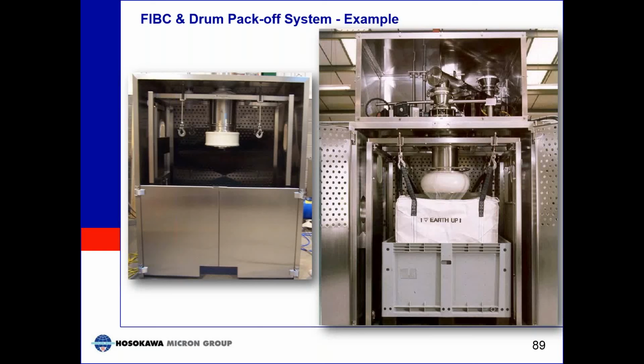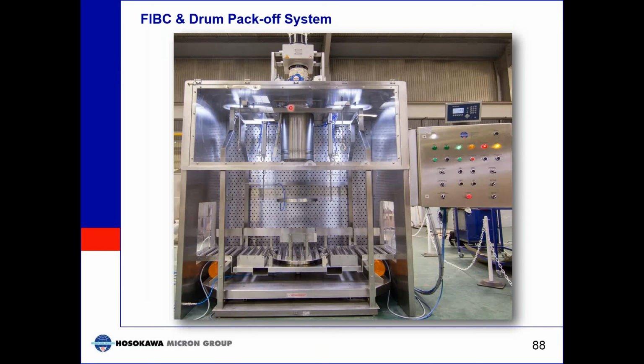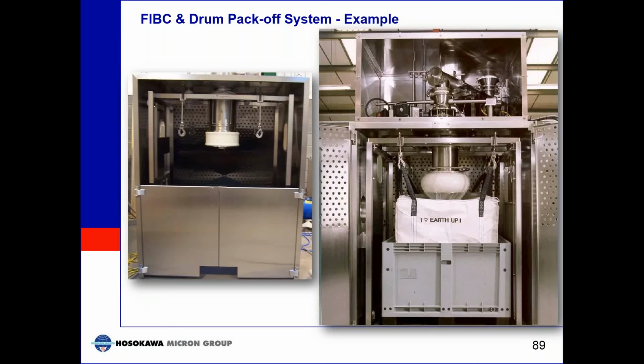In achieving that make-up air, there might be limitations on the HVAC, for instance, so that the room has only got a limited supply of make-up air. In those instances, the ½ meter a second airflow would only be on the aperture between the lower doors and the upper screen. So, as shown here, the gap between the two, where the operator can still have access to the liner and can still tie the liner off, whether it be single or continuous liner, would still achieve the ½ meter a second ingress of air to provide secondary containment to the operator.